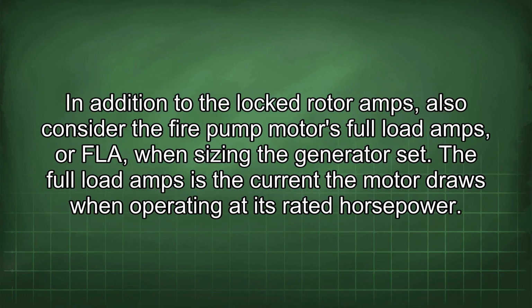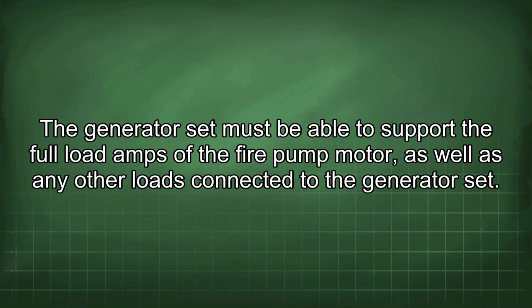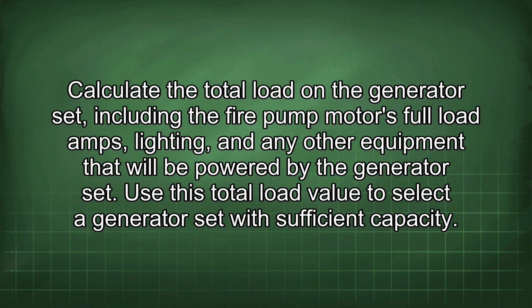In addition to the locked rotor amps, also consider the fire pump motor's full load amps, or FLA, when sizing the generator set. The full load amps is the current the motor draws when operating at its rated horsepower. The generator set must be able to support the full load amps of the fire pump motor, as well as any other loads connected to the generator set. Calculate the total load on the generator set, including the fire pump motor's full load amps, lighting, and any other equipment that will be powered by the generator set. Use this total load value to select a generator set with sufficient capacity.